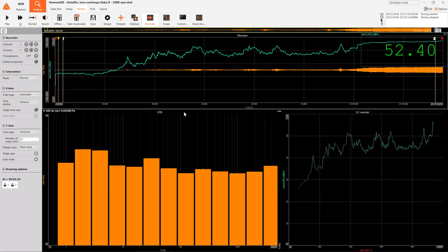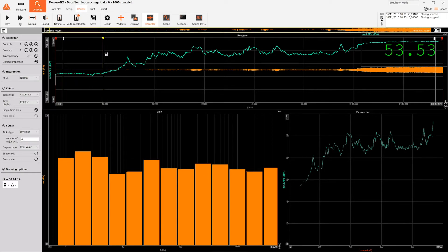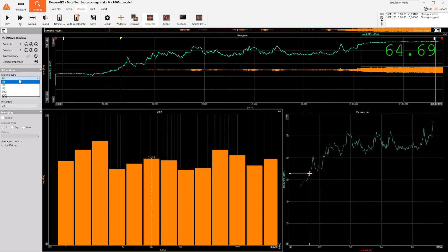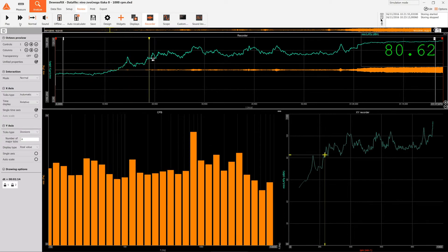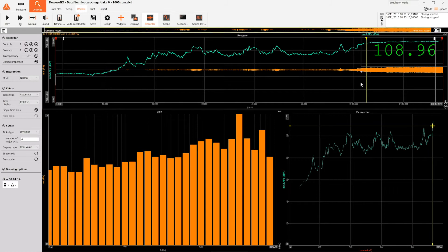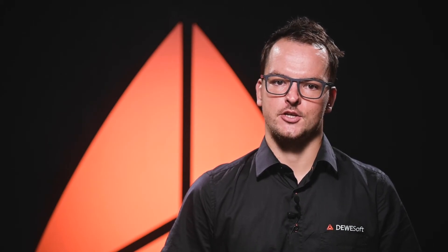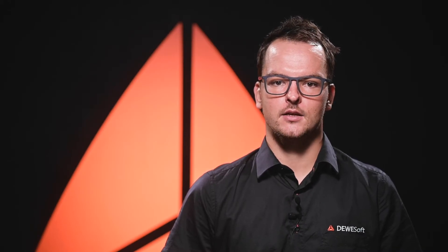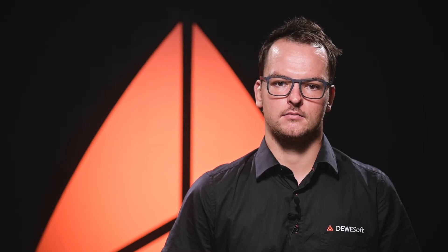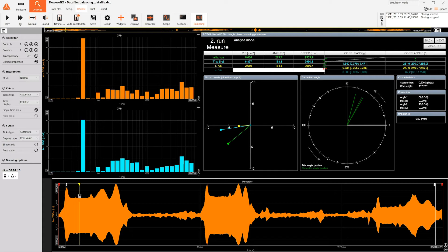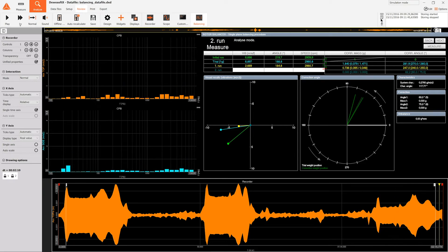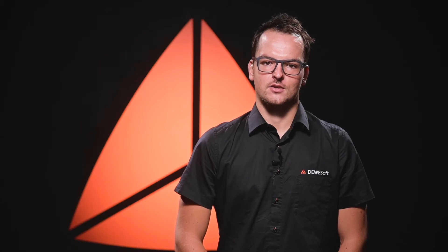A special type of frequency analysis is octave analysis, also called constant percentage bandwidth analysis. Octave analysis is an indispensable tool for sound measurement as well as predictive maintenance and monitoring, due to its logarithmic frequency axis. When monitoring machine condition, signals contain useful information such as noise and harmonic content that are difficult or impossible to detect when their amplitudes are plotted in the time domain. The octave analysis nicely divides the frequency areas into octaves, and peaks in the octave spectrum can show unbalance, blade defects, or bearing faults.